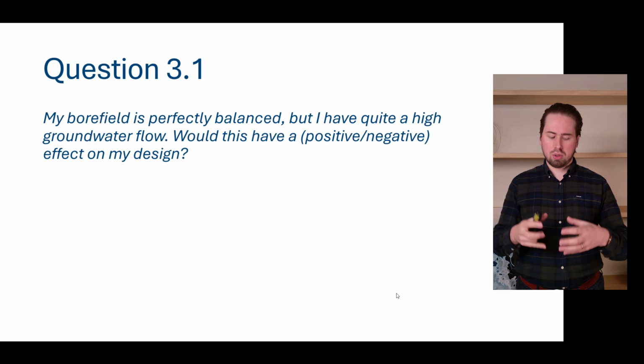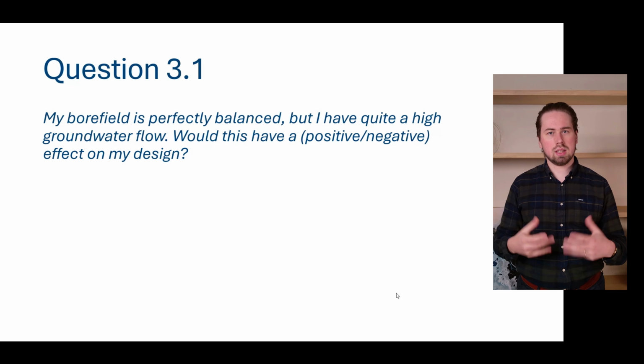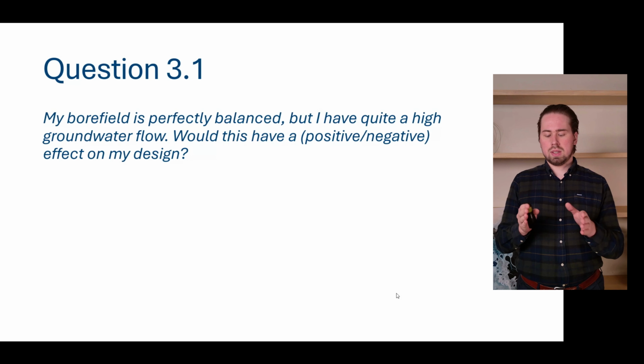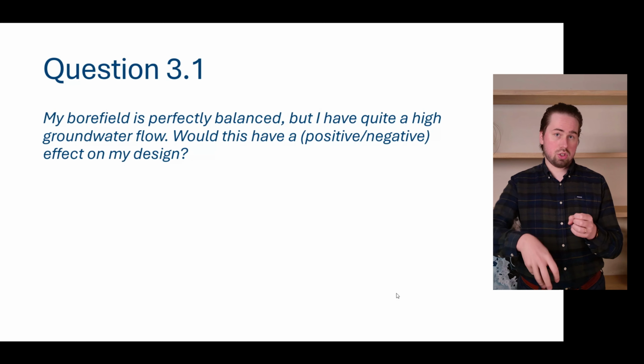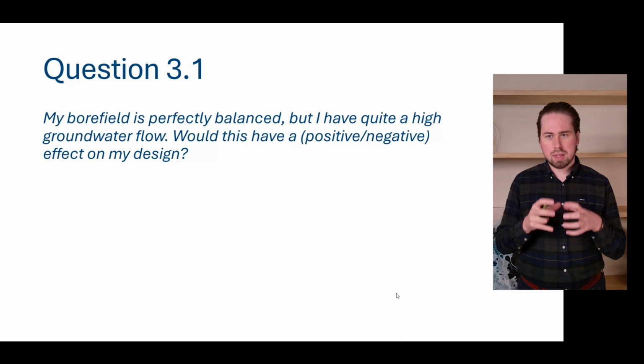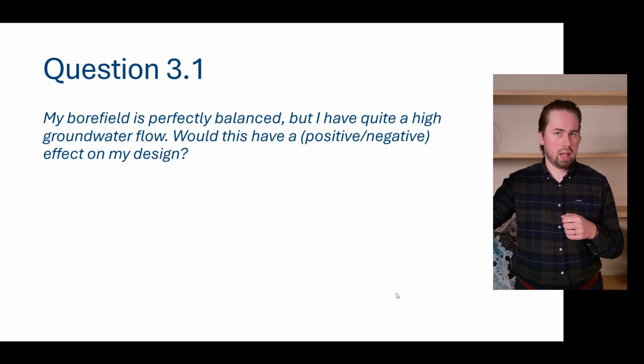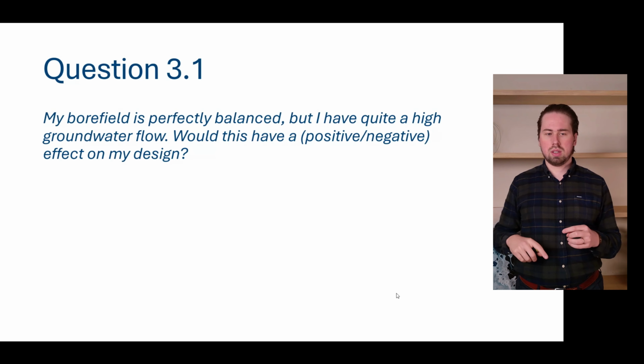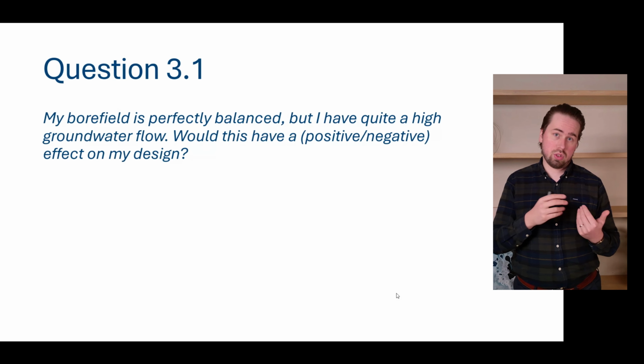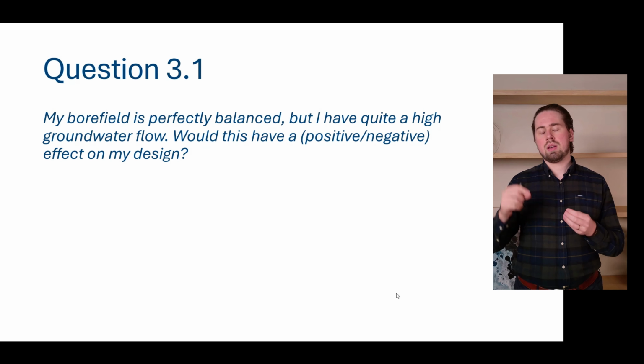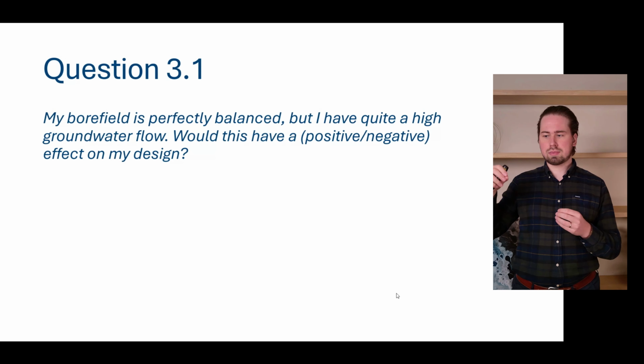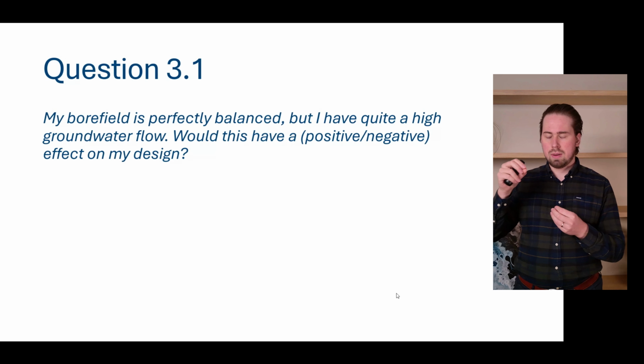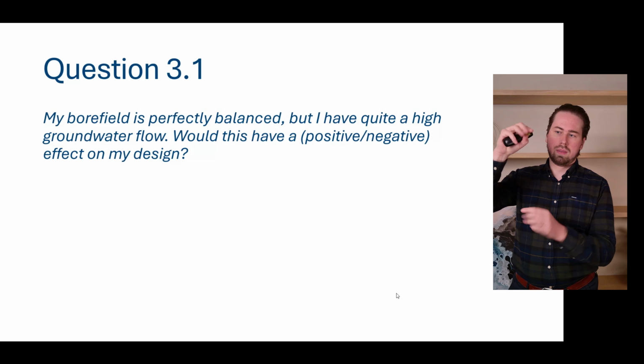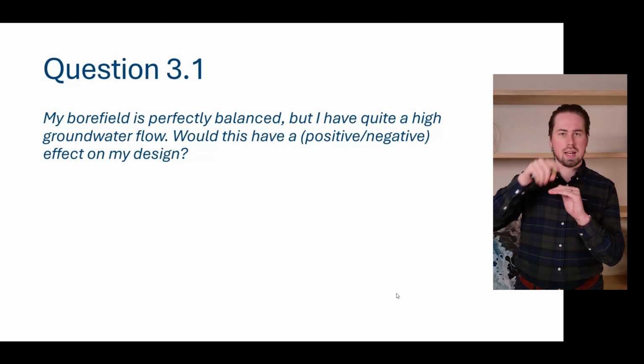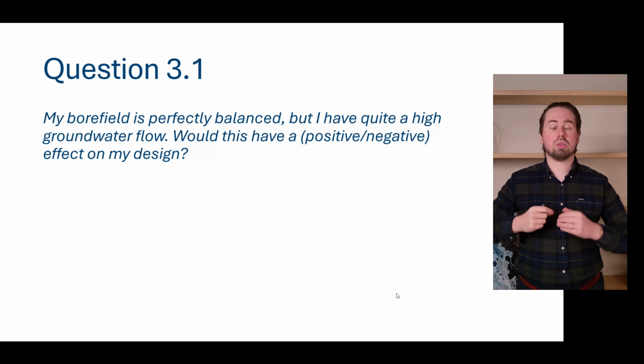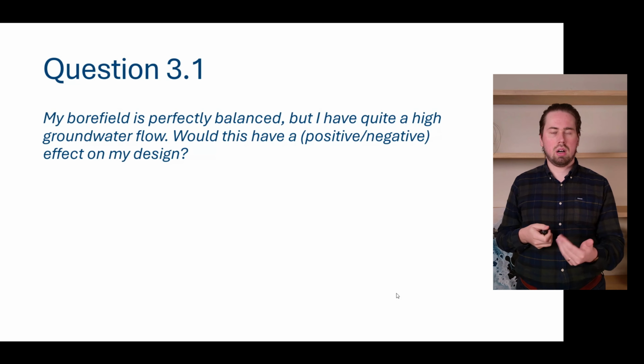Because if you recall, our bore field is really a way to store energy over the seasons. It's a seasonal thermal energy storage system. So what this means is that in winter, we extract heat from the ground, so we store the cold, and we want to keep that cold in order to be able to cool passively or actively our buildings. But if we have a groundwater flow, part of this stored cold, and vice versa the stored heat from summer, will be taken away. So this means that in our temperature profile, since we have this groundwater flow and the energy is not stored as much, our temperatures are actually closer. Our sinusoidal amplitude is actually a little bit smaller. And this could have a negative effect on your design.